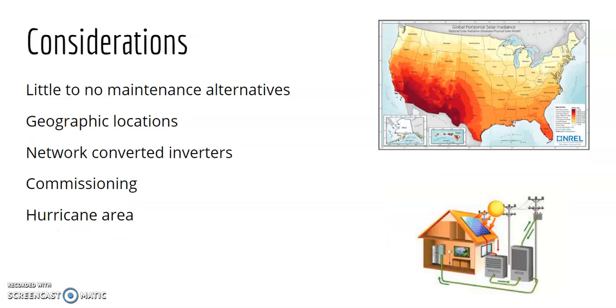One of the first items to consider is to select maintenance alternative equipment that requires little to no maintenance. Although there is a high upfront cost, these pieces won't need to be replaced as often. Another strong setup is to use network connected inverters, allowing for remote testing and updates. As mentioned above, commissioning the project by a third party creates a strong foundation for a successful operations and maintenance plan. The geographic location of the system needs to be considered as well.